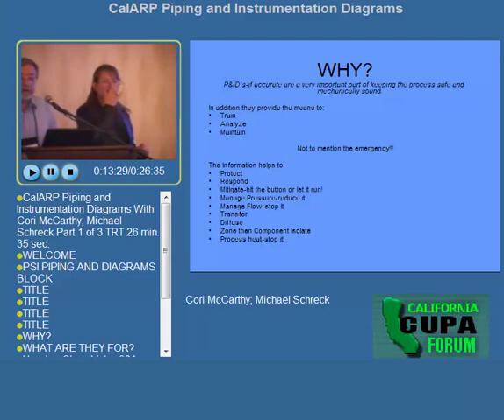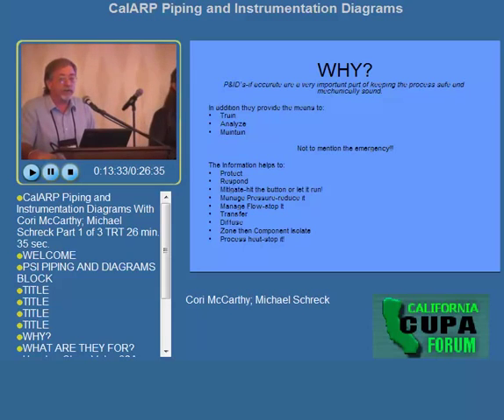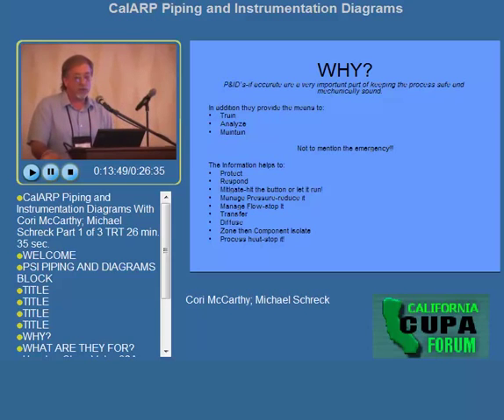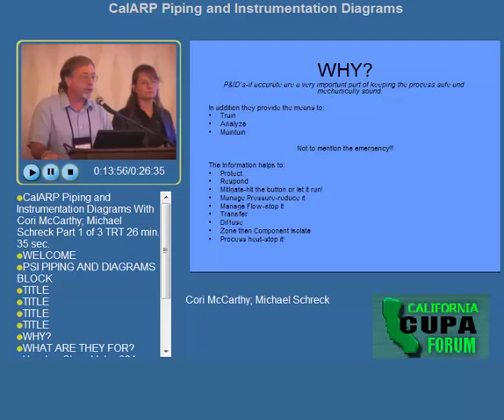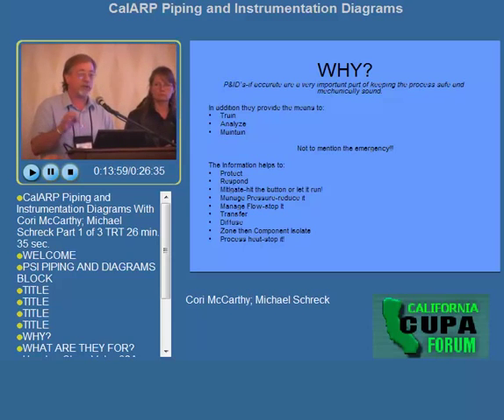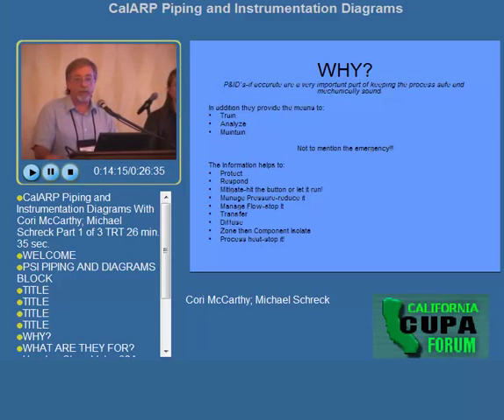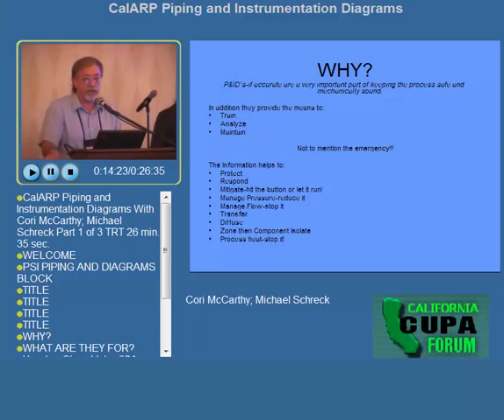How many have seen a fireman's control box and understand why it's there? It's been required by code, went away, then came back. Under the International Mechanical Code 2007, we now have automatic crossover boxes — if there's excessive pressure on the high side, a control valve automatically opens to transfer that pressure to the low side. That is an excellent place for a sectional P&ID, because if a fireman goes to that box and tries to operate it, he's going to see all these valves and may not know which one to turn. A sectional P&ID is critical at locations with critical controls.